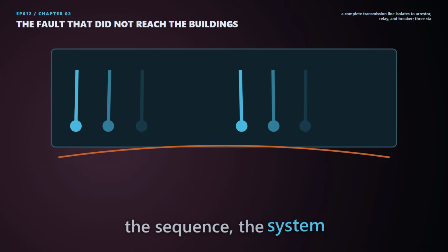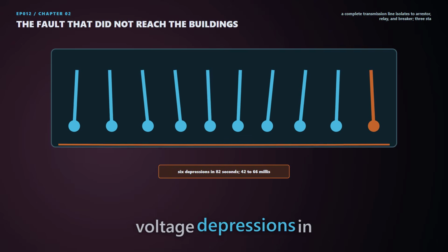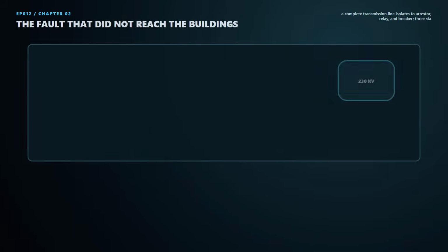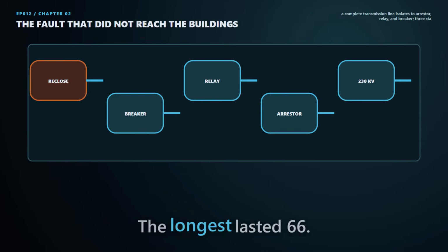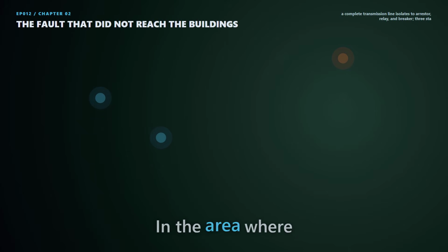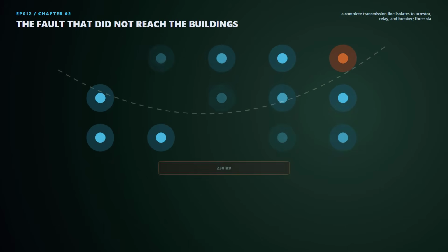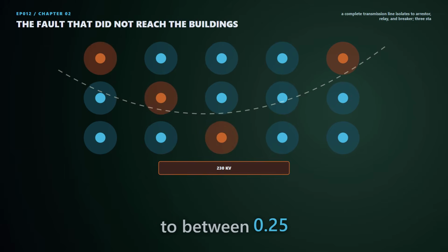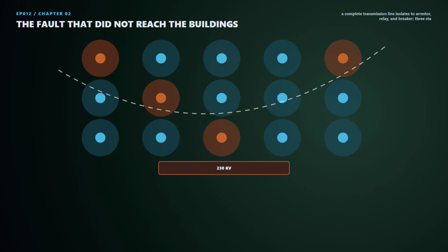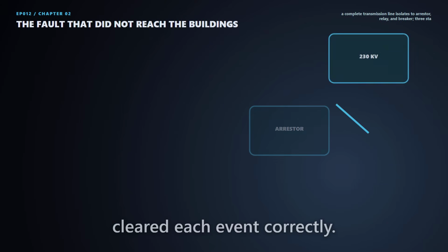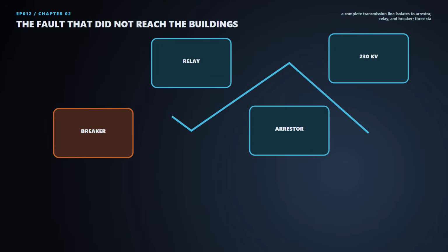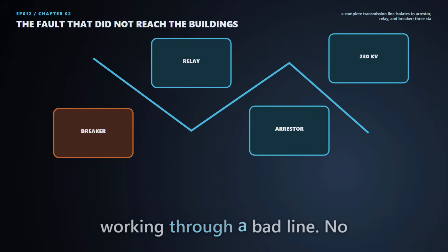Across the sequence, the system experienced 6 short voltage depressions in 82 seconds. The shortest lasted 42 milliseconds. The longest lasted 66. In the area where load later transferred, voltage on the faulted phase fell to between 0.25 and 0.40 per unit. Then the breakers cleared each event correctly. From the transmission side, this was a protection sequence working through a bad line.